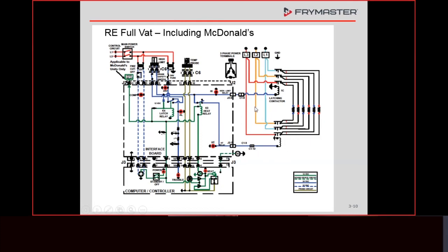All right. When you turn the fryer on and it's not calling for heat, one of the checks that we need to do, and I'd mentioned it earlier, is do an amp draw on all these element wires. And you can do it on the 3-phase, but the element wires are a lot easier to get to. You can do that from the front. Just put your amp meter on there and see if you've got any amp draw. If you do, okay, either we have a contactor that's stuck, or we have an issue where we've got a short in one of these wires.